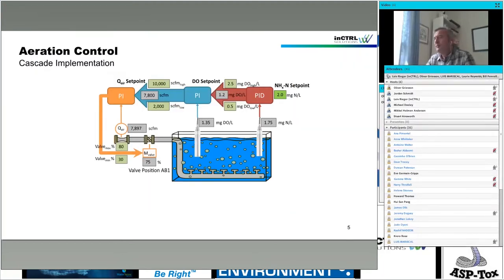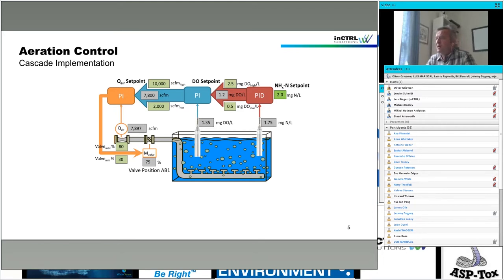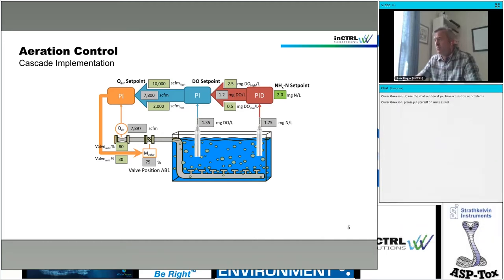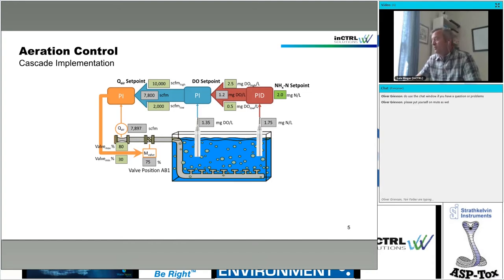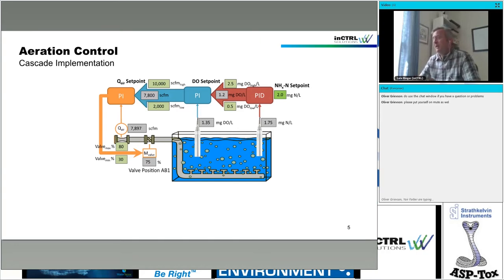To make it a little bit more complex, we discussed a single control loop implementation, and now this is an implementation of an ammonia-based aeration controller, done in the form of a cascade. You have the ammonia control loop, which calculates a DO set point, which is picked up by the DO controller. Then there's an air flow set point, and the air flow controller then calculates a valve position. So it's a full cascade.